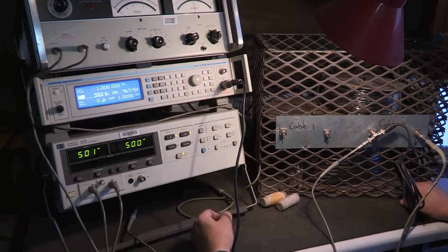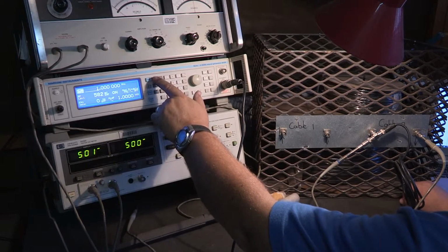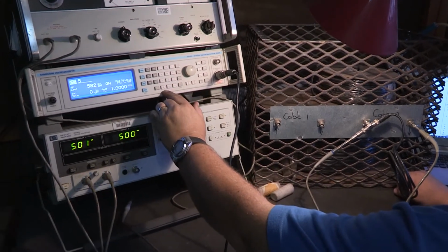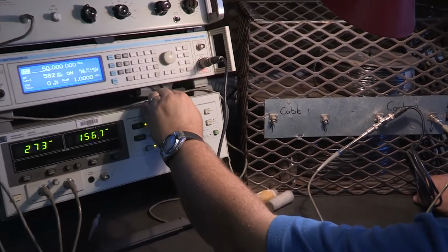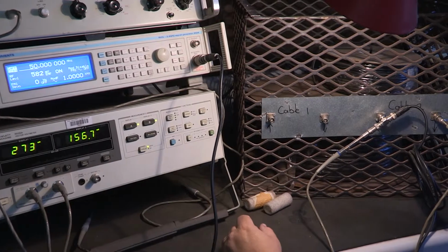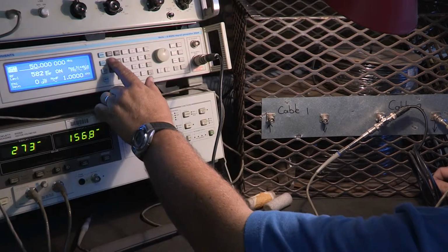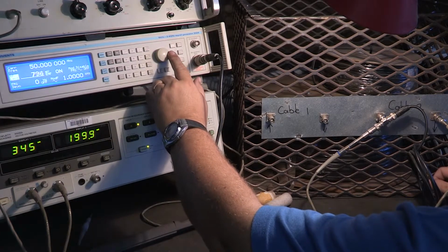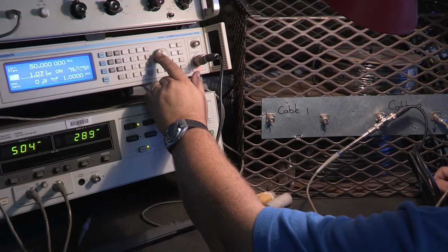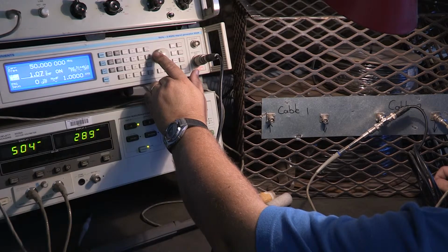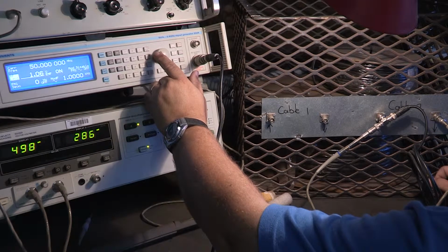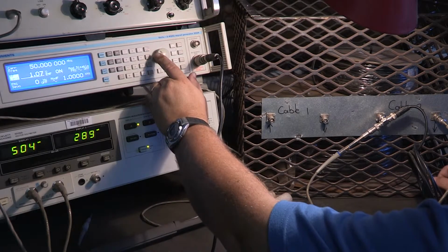So now that we know the setup works, our first frequency that we put in, carrier, is 50 megahertz. You'll notice immediately there is a decrease because of our feeding cable. How do I fix it? Very simple, RF level, adjust it until we get 500 millivolts. Just make it nice and easy. Right, that's almost there. You have to be patient with this thing and just touch it. It's like a nice, easy way of doing that. Close as you can get. Yeah, it's close.